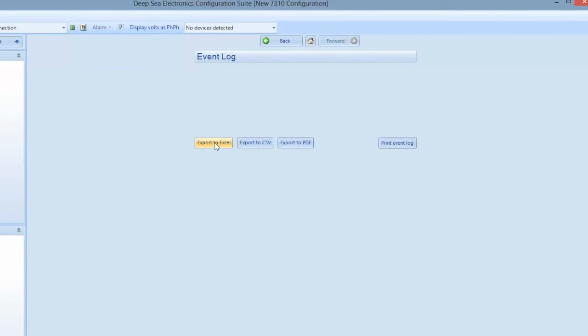If needed, you can export the event log to your laptop and save it for future use. The event log reads directly from the engine ECU. If there is an ECU fault in the machine, the event log will give you the ECU readout and fault code to reference back to.